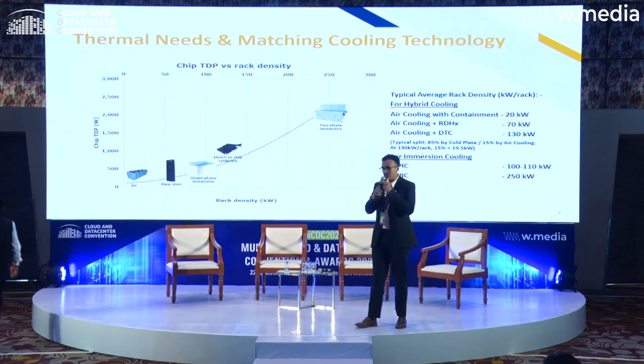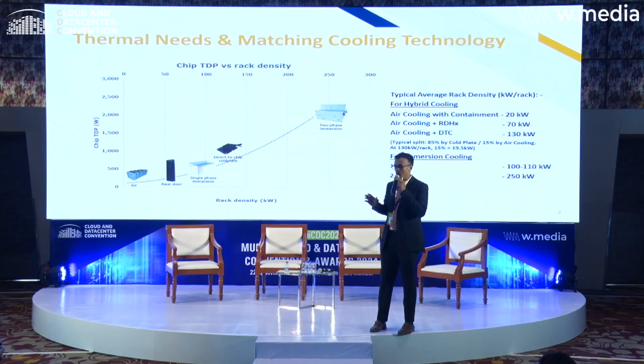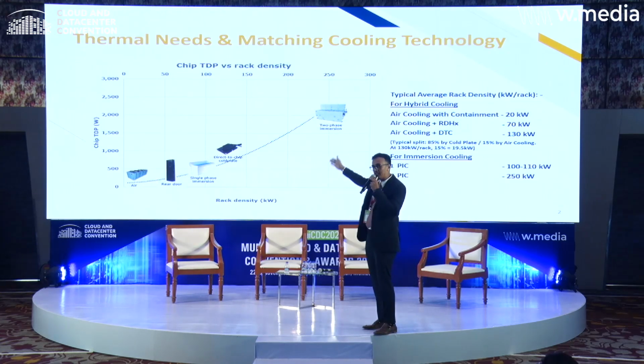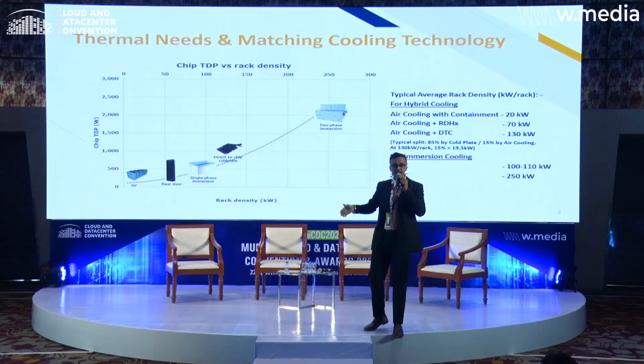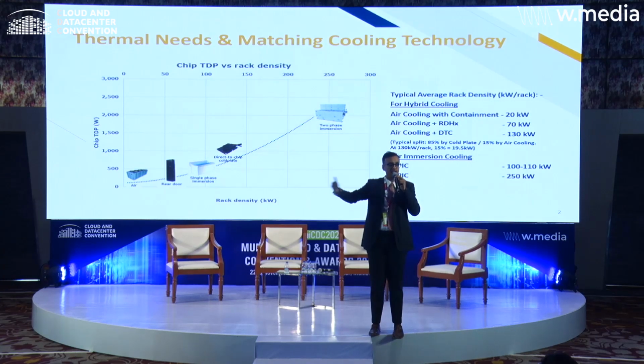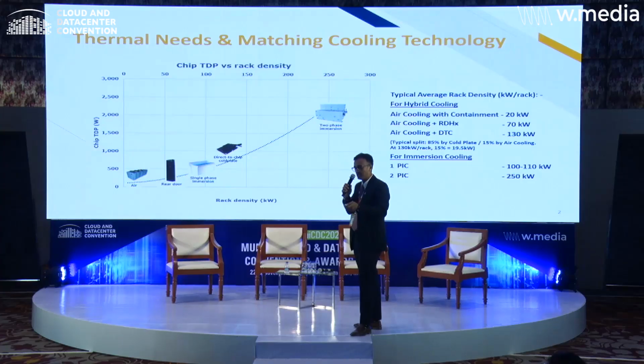So this is the computing need of the world right now. We are at a computing need of up to 50 kilowatts. If you see, all the technologies till now were at air cooling or heat exchanging. But now with the new AI loads coming in and the new compute becoming higher and higher, in the north of 100 kilowatts, air is not going to be able to take care of any of this compute. So we'll go to different modes of cooling, which is liquid cooling, either single phase, or direct to chip, or complete immersion cooling with two phase. That is how the world is going to process data and compute heat in the future.